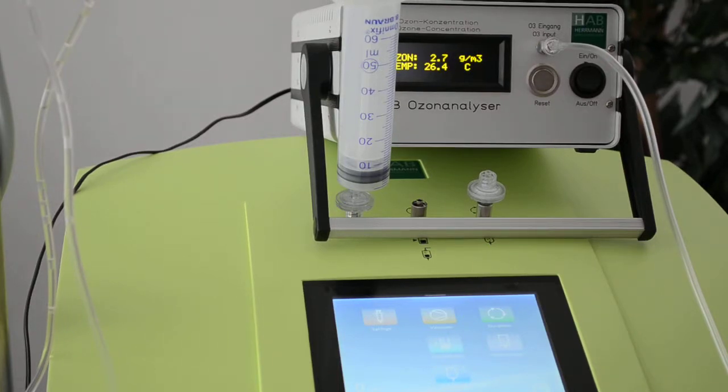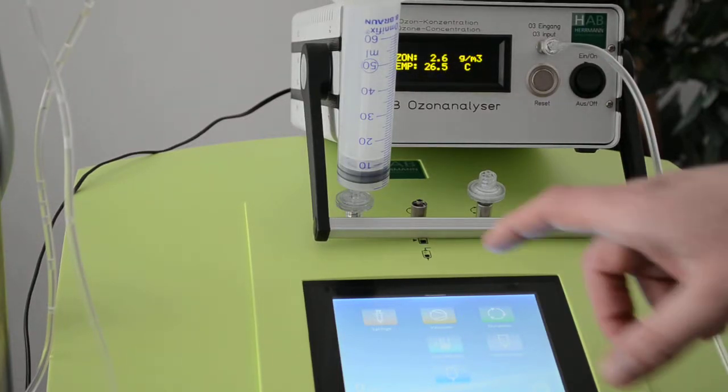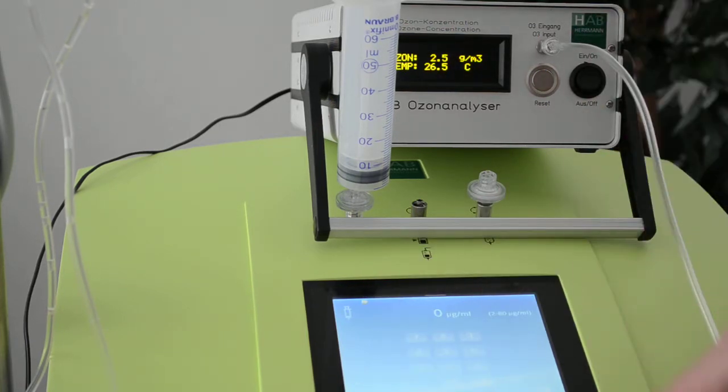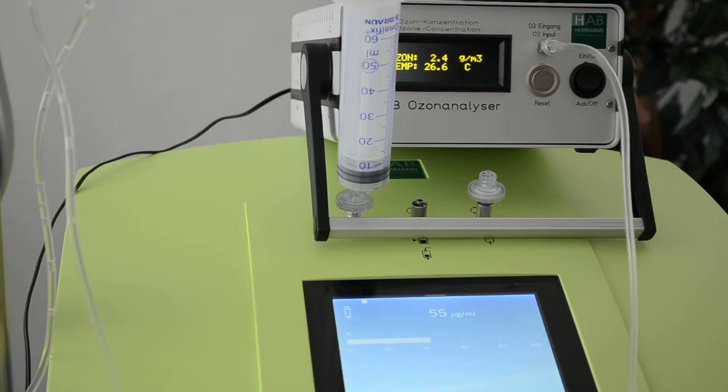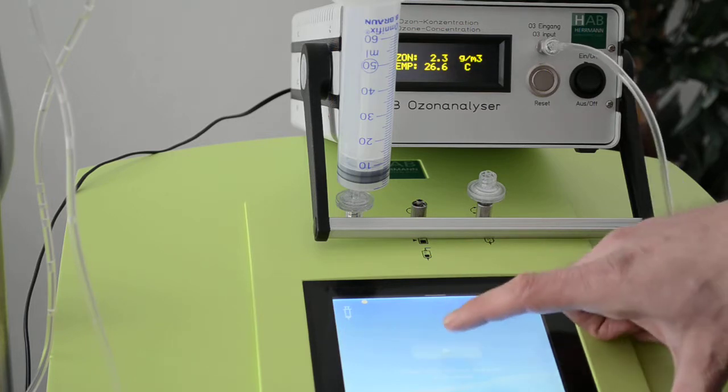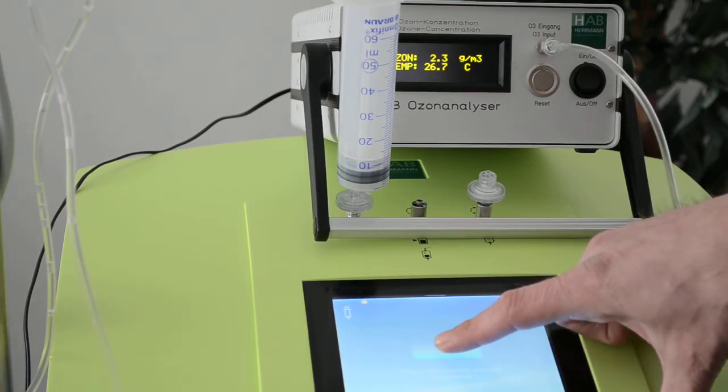Now we will continue with the syringe. I'm choosing the syringe function and putting it in concentration mode. Let's say 55. I confirm. Now the device is creating the ozone concentration, so we will fill the syringe.